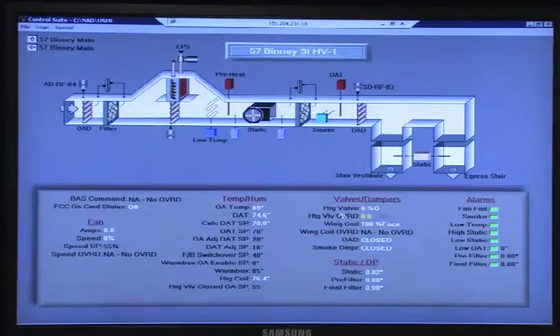There's a hot stairwell pressurization real quick. This is the stairwell pressurization for fire alarm activation in the stairwell. If we have a smoke alarm that goes off, this fires up and pressurizes positive pressurization into the vestibules that go into the stairwells. It pumps air into all those and pressurizes them all. Okay? That's that system there.